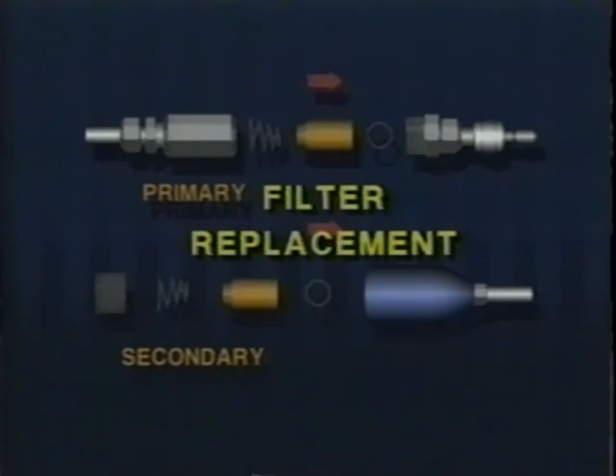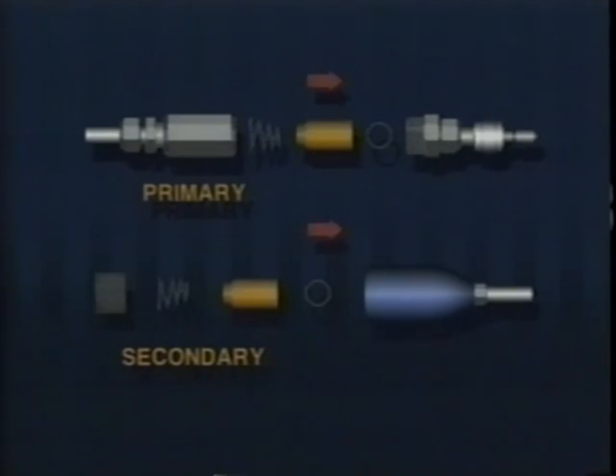The FlamePack 400 is equipped with two filter holders. Both are located in the sample probe. The primary filter is in the upper housing. The secondary filter is in the lower cone. The primary filter is absolutely essential to proper operation. Use of the secondary filter is optional, but is recommended in dusty environments.